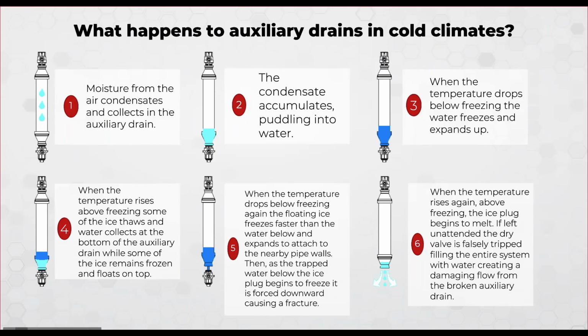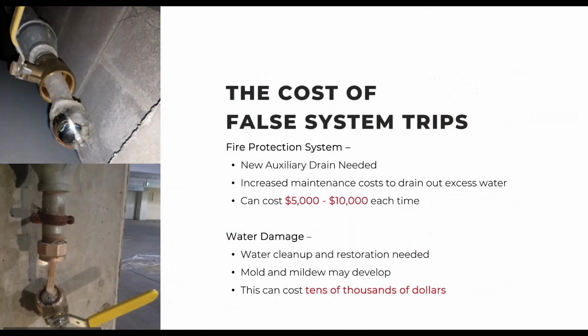So when people say, well, they freeze and break, we try and explain to people, it's actually they freeze, they thaw, and then when they freeze again is what causes all the problem. It's when the units freeze and then when they thaw, that ice floating in the thawed water freezes again, and due to the hydraulic pressure of the expansion, when the ice freezes, it either ruptures the seam on the pipe or possibly cracks the reducer, or it may have so much force that it actually blows apart the valve at the bottom of the unit.